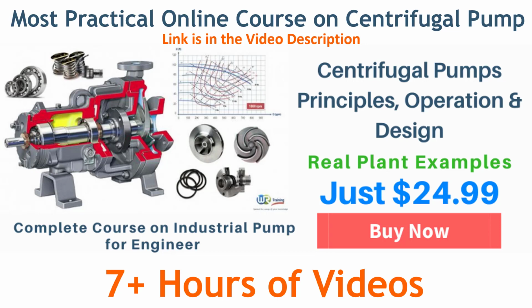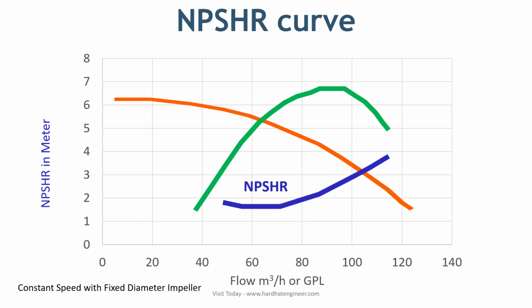The next curve is the NPSH required curve. Net positive suction head at the pump suction is necessary to prevent cavitation in the pump. From the curve, you can see that the NPSH requirement will increase with the higher flow rate. This is like more liquid with higher head has to enter the pump when you push more liquid out.